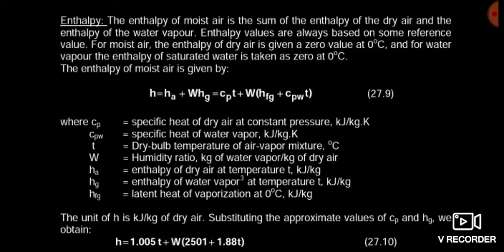Because moist air contains air plus water. Here W is the humidity ratio, HFG is the enthalpy of latent heat of vaporization — the amount of heat required to change the state of water to vapor. CpW is the specific heat of water vapor, and T is the temperature of the air-vapor mixture in degree Celsius. When we put the values of Cp, HFG, and CpW, we get the equation: H = 1.005T + W(2501 + 1.88T).